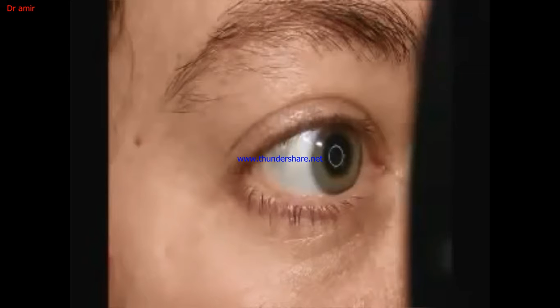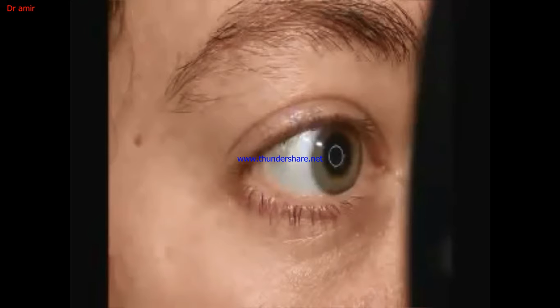Once this is done, occlude the left eye. Turn the instrument to point directly at the eye being measured. Looking from the left side of the instrument, you will see a bright white ring in the center of the patient's right eye. If the bright white ring is not in the center, you may use the elevation knob to center the ring. Once the correct position has been established, instruct the patient to fixate on the green light inside the instrument.